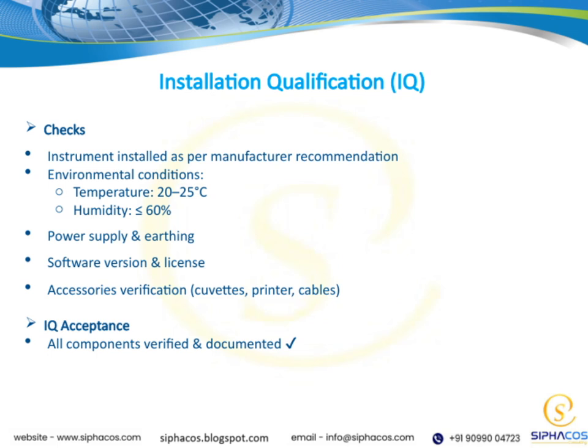This is a crucial step to ensure everything is set up correctly from the start. First, we verify that the instrument has been installed according to the manufacturer's recommendations. This means following the specific guidelines to make sure the equipment is positioned and assembled properly. Next, we look at the environmental conditions. It's important that the temperature stays within 20 to 25 degrees Celsius and humidity levels are at or below 60%. These conditions help maintain the instrument's optimal performance and longevity.